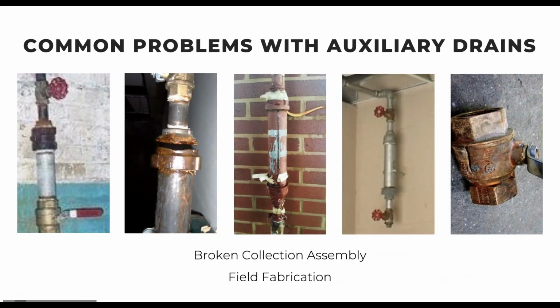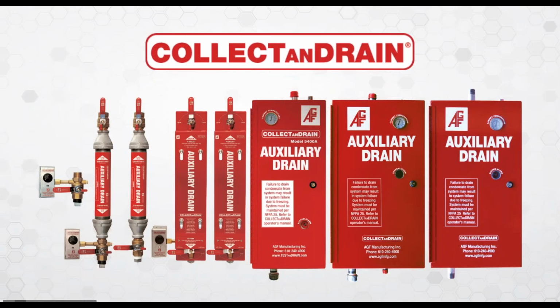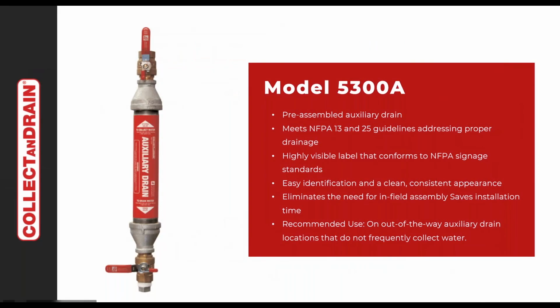These units may be assembled through a variety of wrongly installed parts, and all of that leads to why we introduced the collect and drain product line. And it starts first and foremost with our model 5300. So like you saw in the NFPA 13 code drawing, here we're providing a factory built and tested 2 valves, 2 reducers, and a 1-foot piece of 2-inch pipe, exactly how code requires it. And we added in the required necessary signage so that these things are bright red. They've got this vinyl wrap around them so you know where they are. And this is just a great thing for contractors so that they don't have to worry about building these units in the field. They can get this product right out of the box.